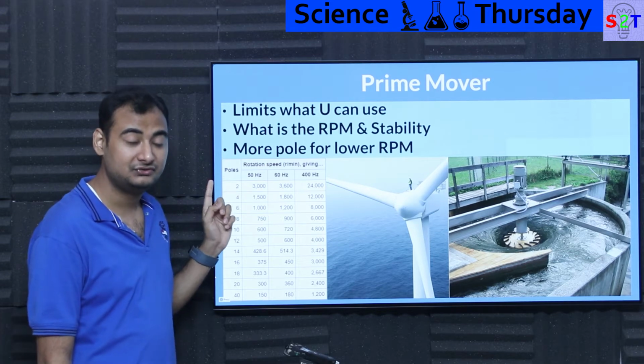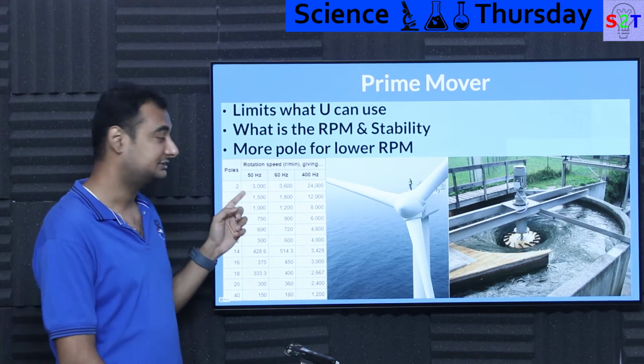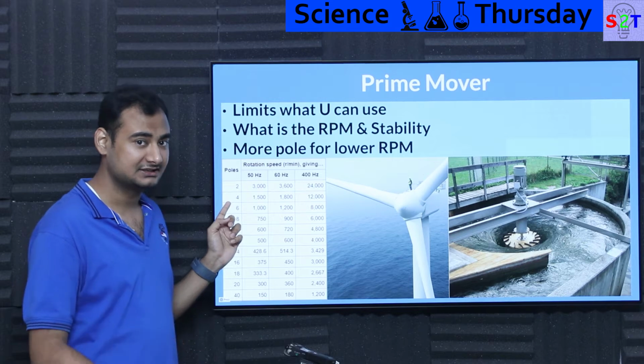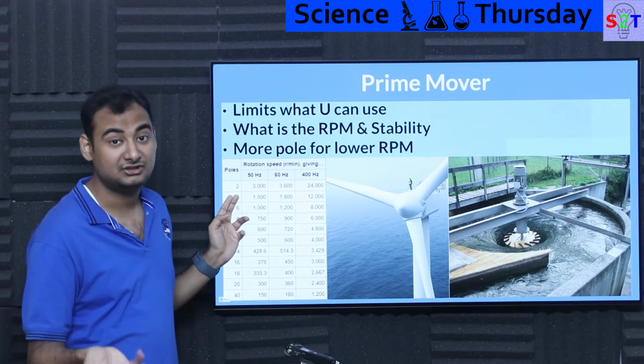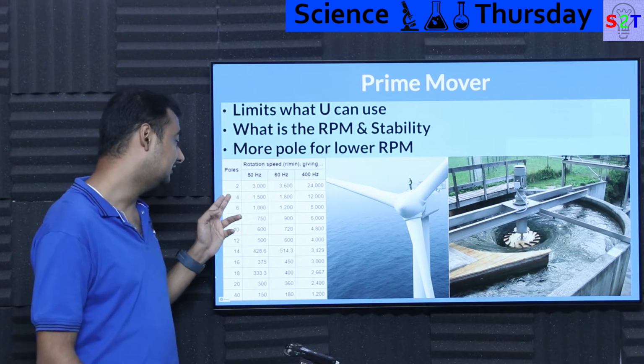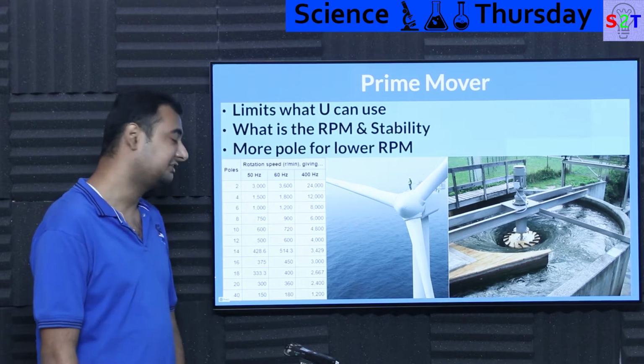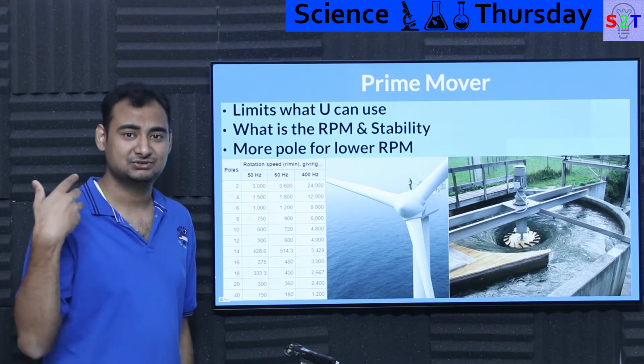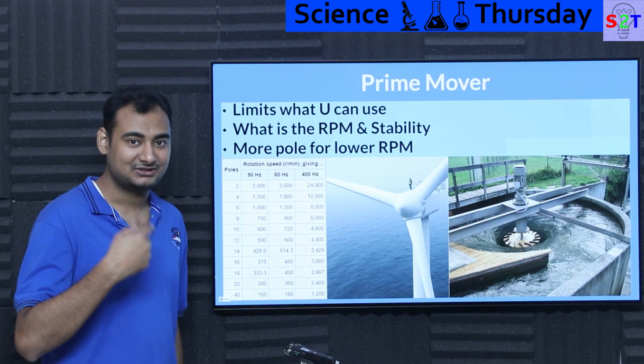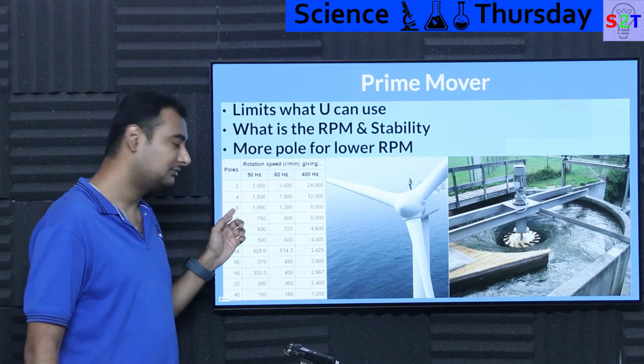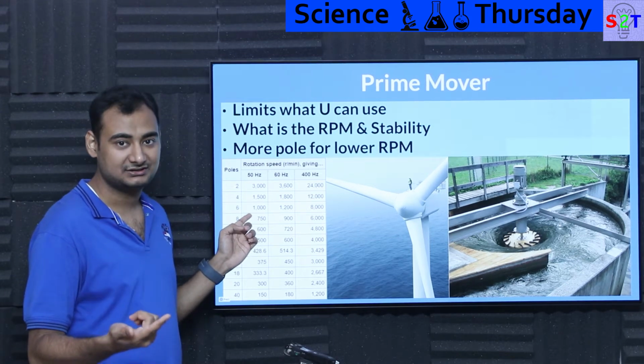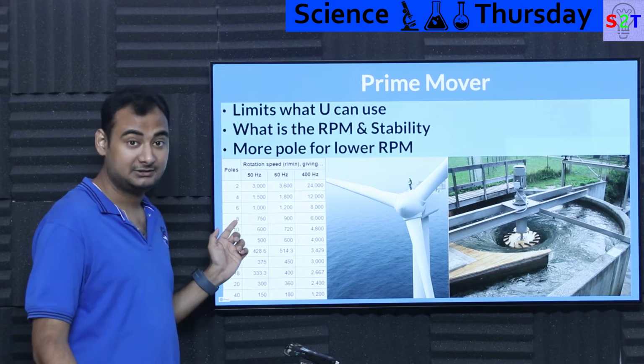If you want to produce 50 hertz electricity, you need 3000 RPM, and petrol generally gives you that RPM. But with a diesel system, which is lower RPM, you need 4 poles, because that's 1500 RPM. But if you want to use an induction motor as a generator and your RPM isn't high, you'll go for 6 pole, which only requires just over 1000 RPM, or 8 poles for 750 RPM.